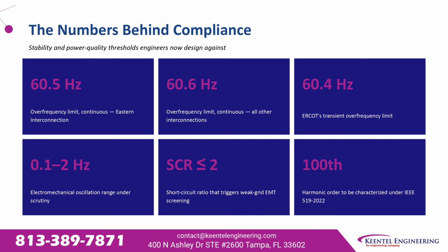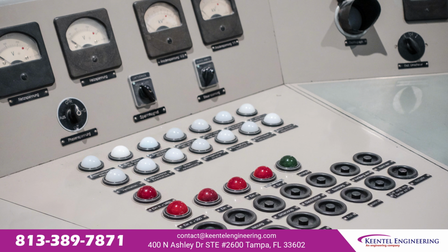A handful of numbers now define compliance. 60.5 Hz is the continuous overfrequency limit in the Eastern Interconnection, 60.6 Hz everywhere else, and ERCOT sets a 60.4 Hz transient limit. 0.1 to 2 Hz is the electromechanical oscillation range under scrutiny. A short-circuit ratio of 2 or below triggers weak grid electromagnetic transient screening, and harmonics now have to be characterized out to the 100th order.